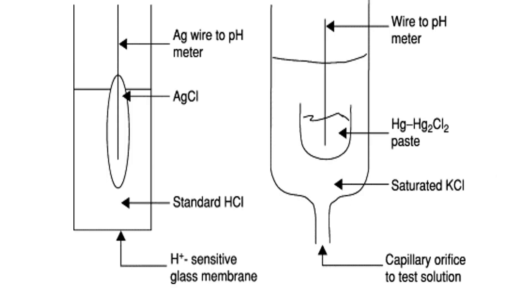A pH meter consists of two electrodes: a measuring electrode and a reference electrode. The measuring electrode has a tip at the bottom with a membrane through which hydrogen ions penetrate. It consists of a silver rod with a silver chloride paste, immersed in a standard HCl solution. The reference electrode consists of a mercurous chloride paste immersed in a saturated potassium chloride solution. It is sensitive to hydrogen ions, and when they come in contact, a potential difference is created.